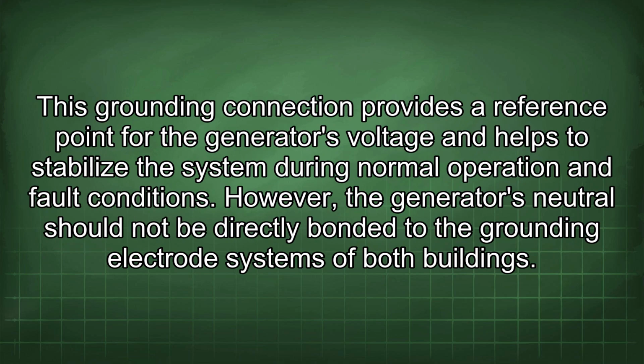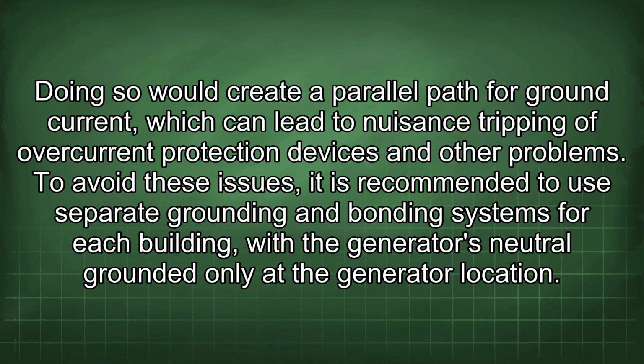This grounding connection provides a reference point for the generator's voltage and helps to stabilize the system during normal operation and fault conditions. However, the generator's neutral should not be directly bonded to the grounding electrode systems of both buildings. Doing so would create a parallel path for ground current, which can lead to nuisance tripping of overcurrent protection devices and other problems. To avoid these issues, it is recommended to use separate grounding and bonding systems for each building, with the generator's neutral grounded only at the generator location.